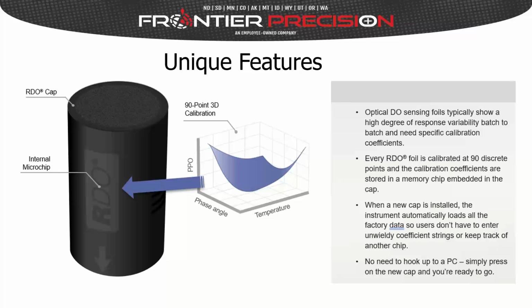The sensing cap has some foils that are bonded together in the top of it. Each batch of caps that is created undergoes extensive calibration procedures, where there's a 90-point three-dimensional calibration looking at the phase angle, temperature, and the partial pressure of oxygen. Naturally, there's a lot of information that goes into this, but to make this easier for the user when they're replacing those caps, In Situ puts a really small internal microchip inside of this cap. So every 2 years when you replace a cap, you just pull the old one off and snap a new one in place, and that microchip does two things for you. It loads all of the new calibration coefficients for that cap, and it tells you the date and time it was installed.